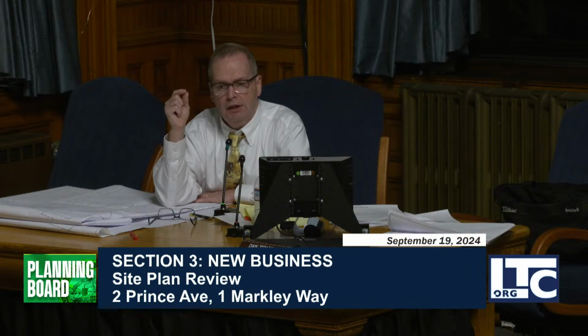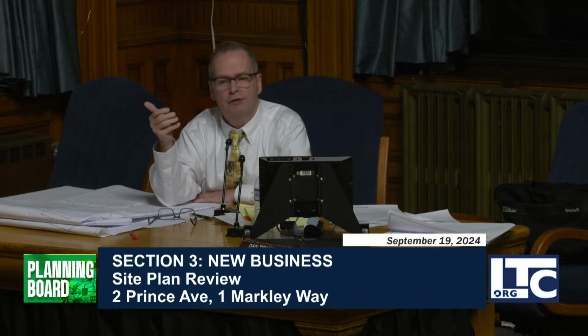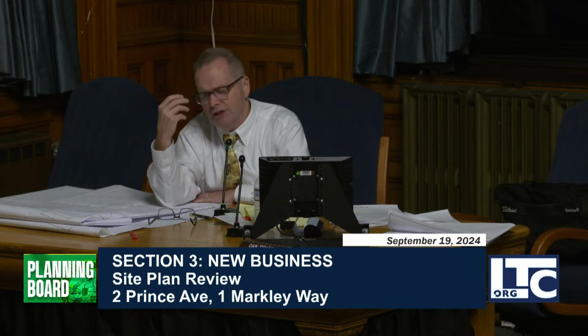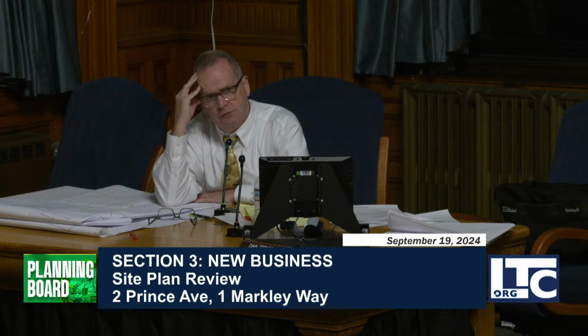Let's get to the generators. I keep hearing different things - that they're used minimally, and then that no, they burn all the time, they test them all the time. Can you speak to that? Yeah, so our testing protocols are 5 minutes per generator per week. That maintains the generator to make sure it's still running and will start on a call.